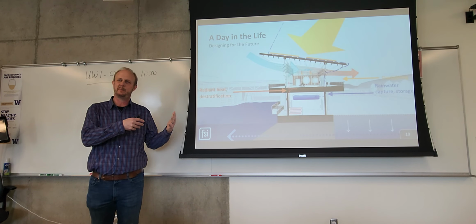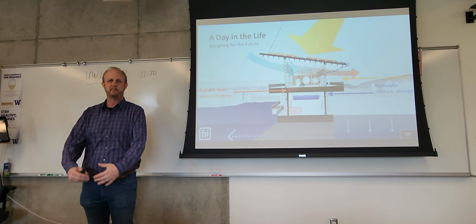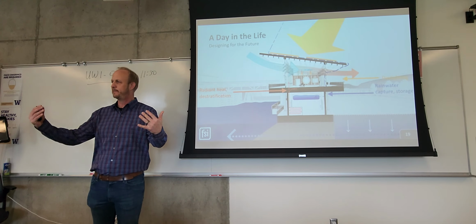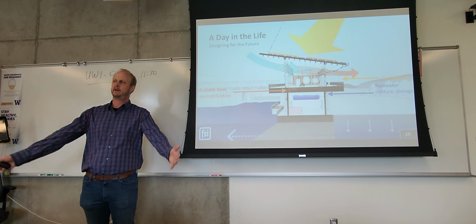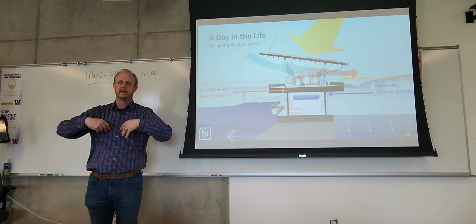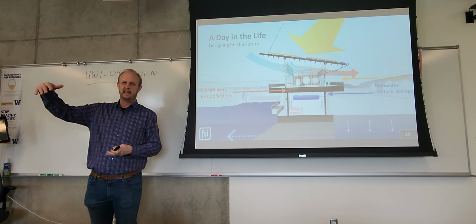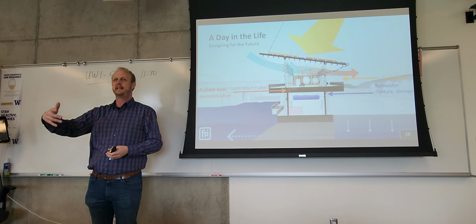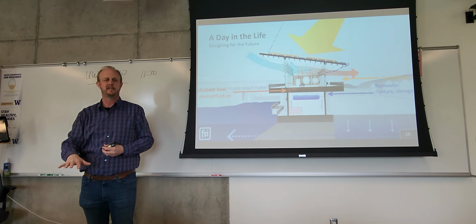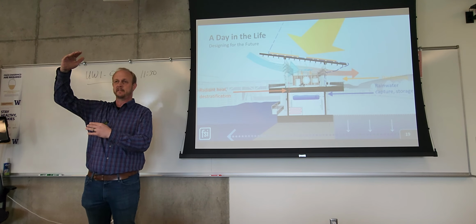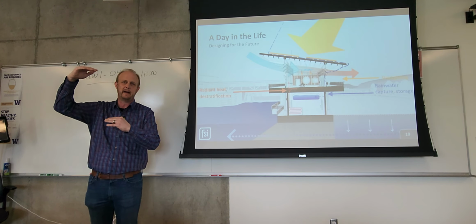And the reason we do that in this building is every time they load the ferry, they open up the doors and they sit open for 10 minutes, and you have this rush of cold air in the winter that comes in, and that air then needs to get heated up again. So that allows us to have a lower temperature, which saves us energy by not having to constantly raise it an additional 5 degrees.